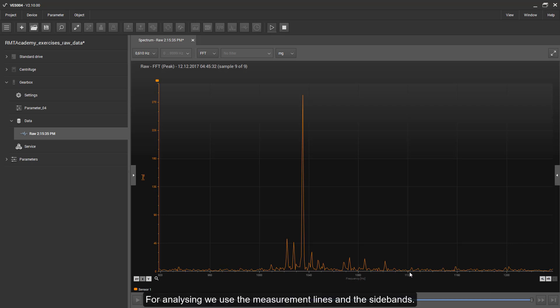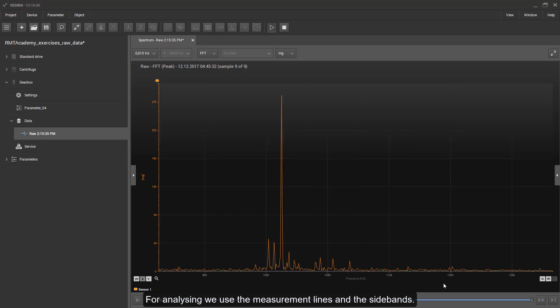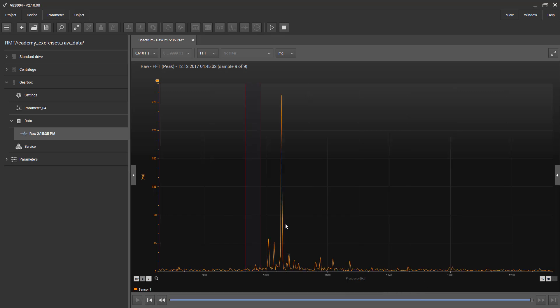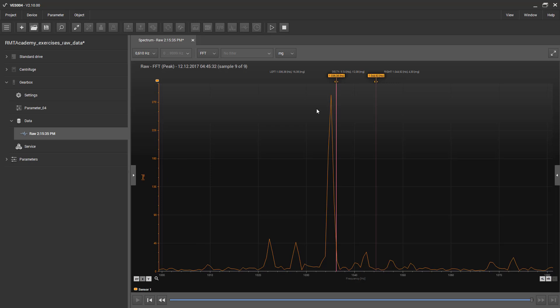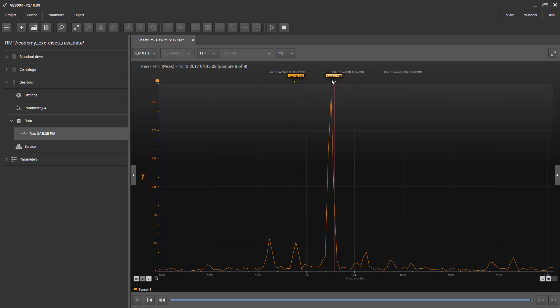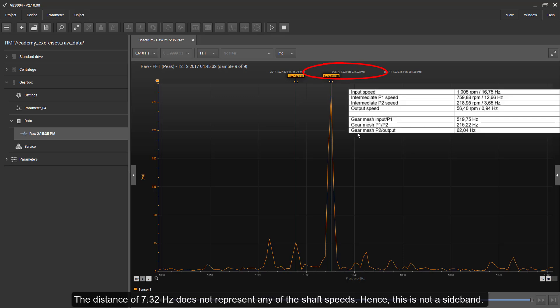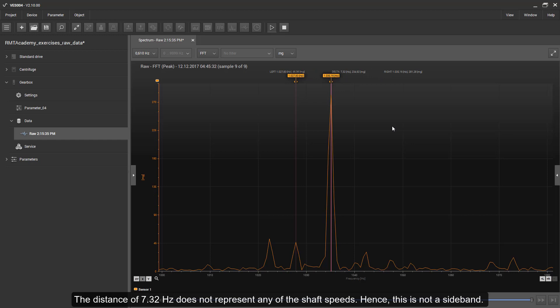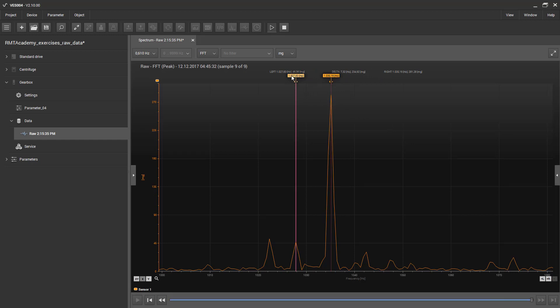For analysing, we use the measurement lines and the side bands. The distance of 7.32 Hz does not represent any of the shaft speeds, hence this is not a sideband.